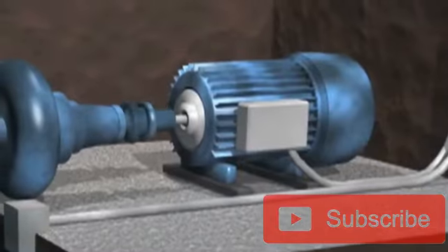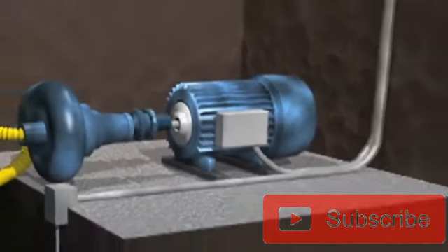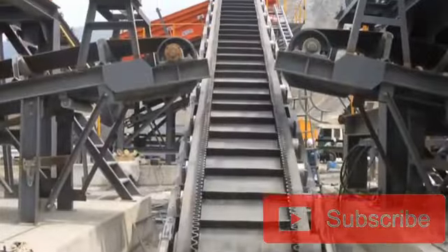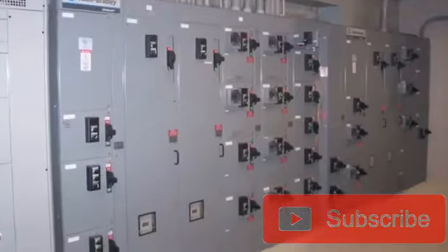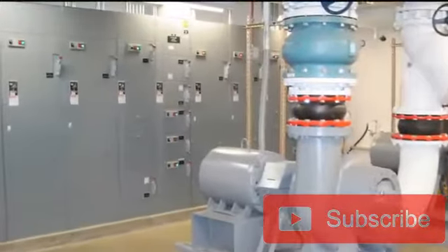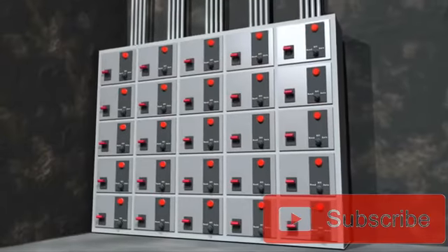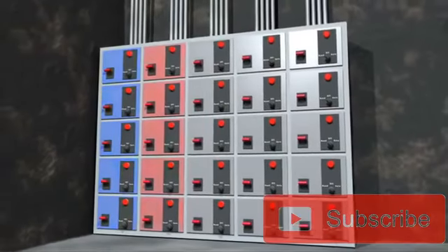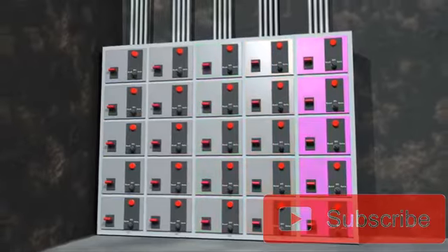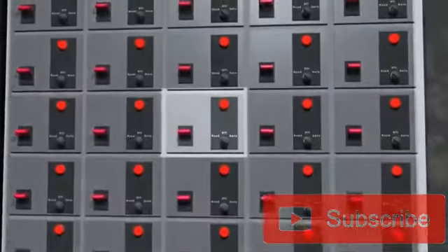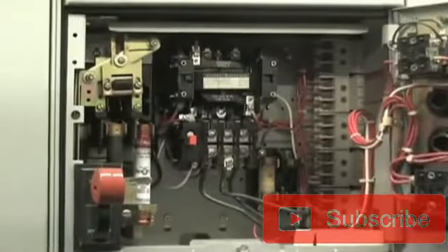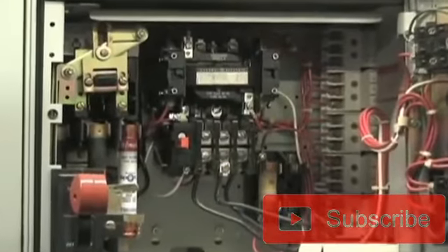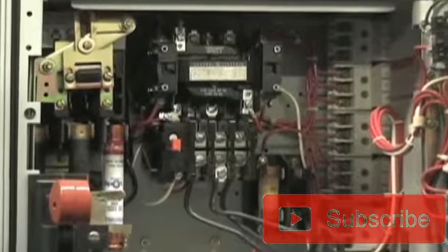In almost every facility there are electric motors. Motors are used in pumps, machinery, conveyors, elevators, and the list is endless. In order to distribute power to motors, the electrical distribution system has motor control centers, or MCCs. These MCCs are made up of a series of sections. Each section contains buckets. Each bucket is assigned to a specific motor. A MCC bucket contains many things to operate the motor. There can be computer logic boards, or PLCs, transformers, contactors, and other control devices to operate the motor.